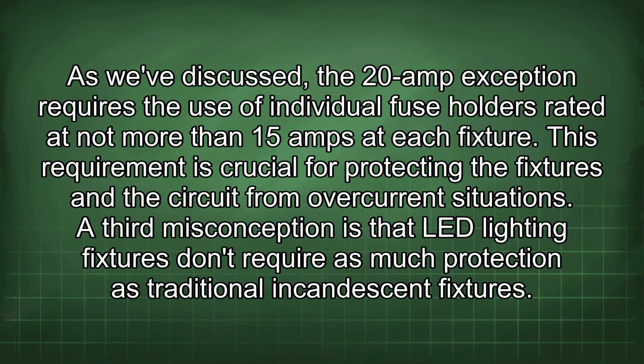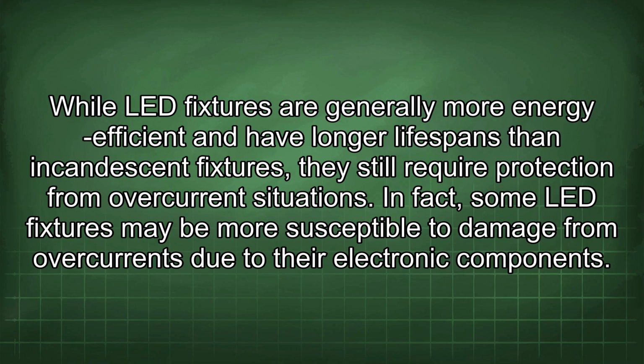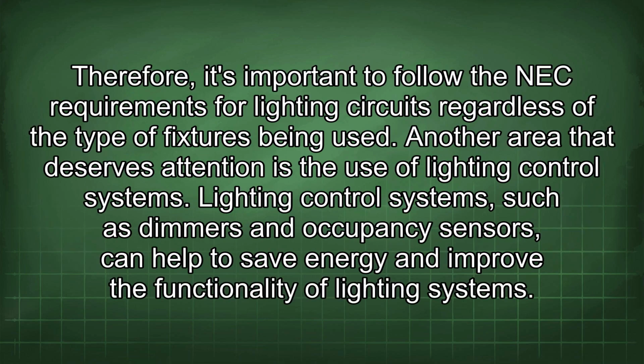A third misconception is that LED lighting fixtures don't require as much protection as traditional incandescent fixtures. While LED fixtures are generally more energy efficient and have longer lifespans than incandescent fixtures, they still require protection from overcurrent situations. In fact, some LED fixtures may be more susceptible to damage from overcurrents due to their electronic components. Therefore, it's important to follow the NEC requirements for lighting circuits regardless of the type of fixtures being used.